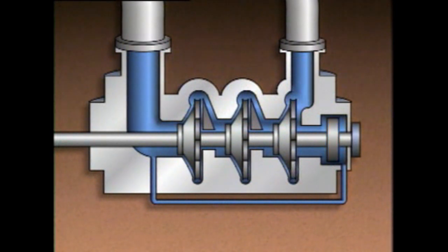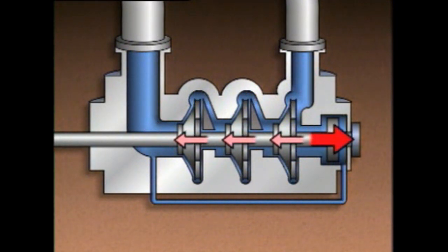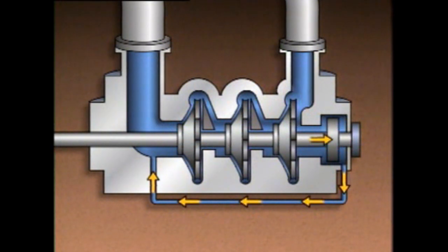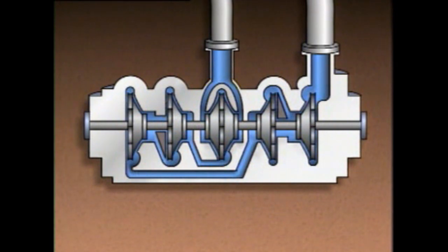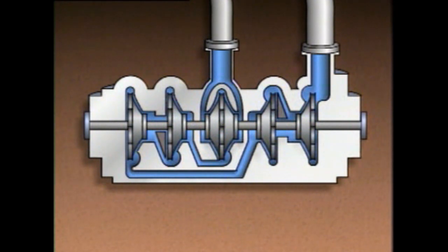One pump uses a balance piston: during operation, fluid leaving the pump flows along the shaft and exerts pressure against the balance piston, tending to force the shaft away from the suction eyes and reducing total thrust. Fluid that passes by the balance piston is returned to the suction side of the first stage. In another pump, the arrangement of impellers offsets axial thrust. Process liquid enters the first stage impeller from both sides, equalizing pressure. The suction eyes for the second and third stage impellers face opposite the fourth and fifth stage impellers, so their axial thrust forces cancel each other out, keeping axial thrust to a minimum.